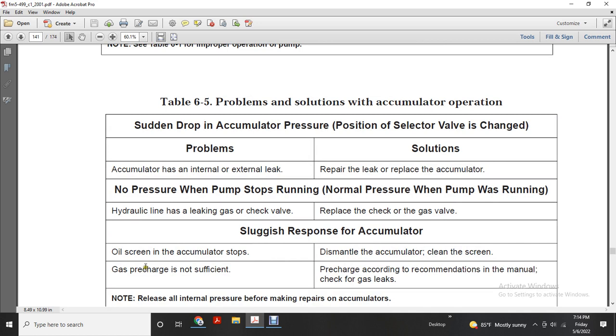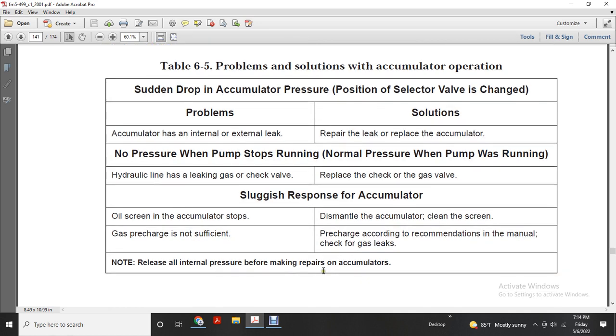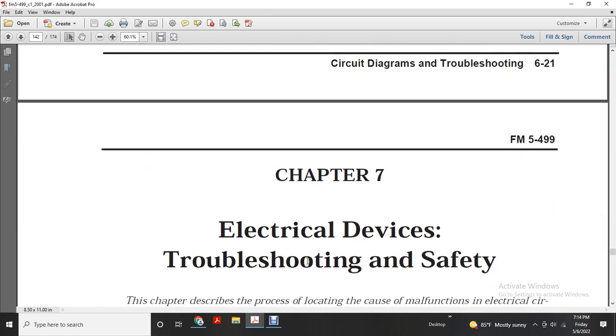Clean the screen. Gas precharge is not sufficient. Precharge according to the recommendation in the manual. Check for gas leaks. Note: release all internal pressure before making repairs on the accumulators. Chapter 7, Electrical Devices, Troubleshooting, and Safety.